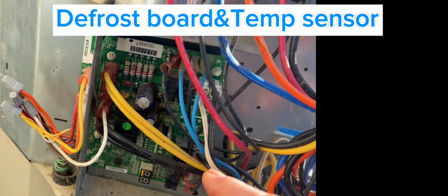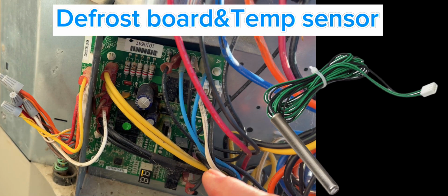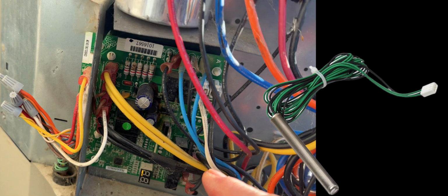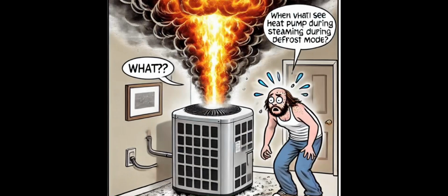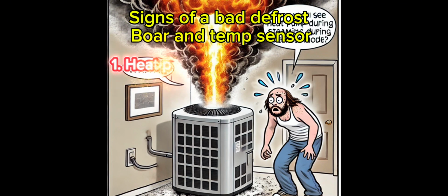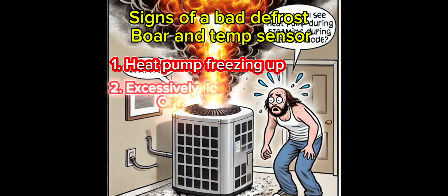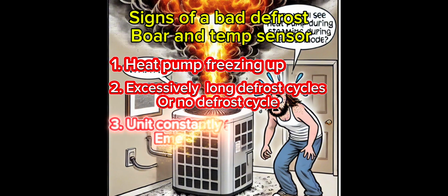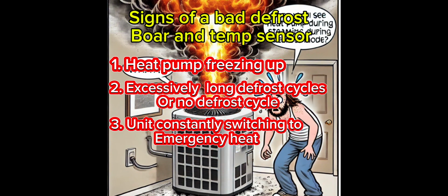Have you ever wondered why your heat pump sometimes turns into an ice block? Well, the defroster board and the sensors prevent that by detecting ice buildup and triggering a defrost cycle. But if the defrost board or the temp sensor fails, your heat pump might freeze up completely, leading to poor efficiency, constant running, or even complete failure.